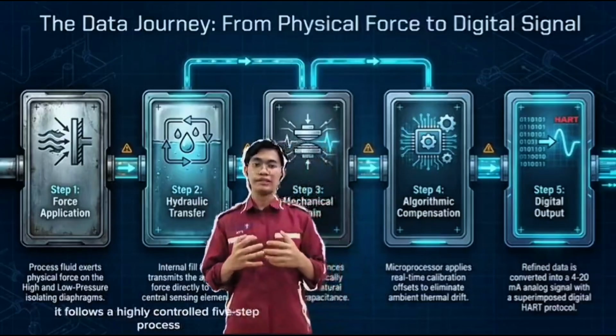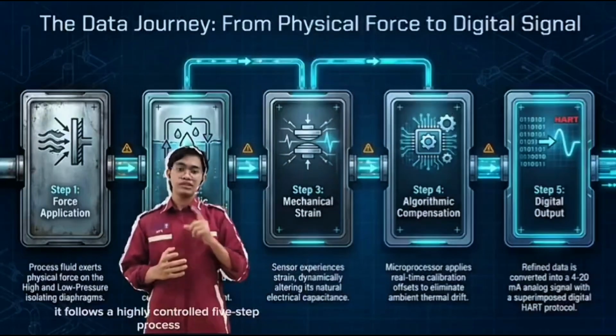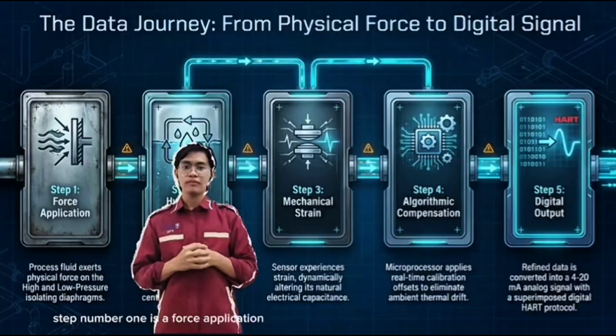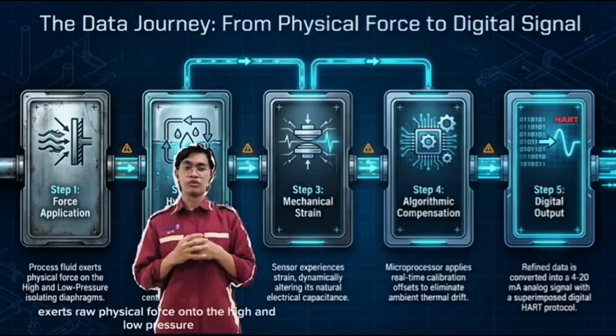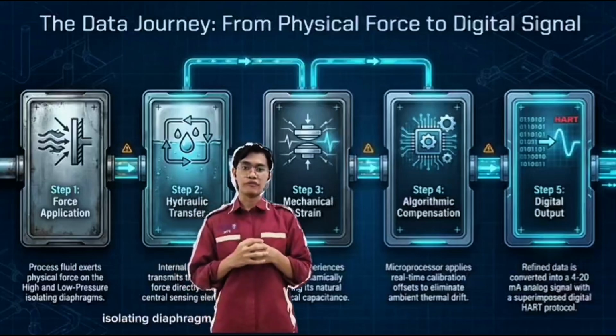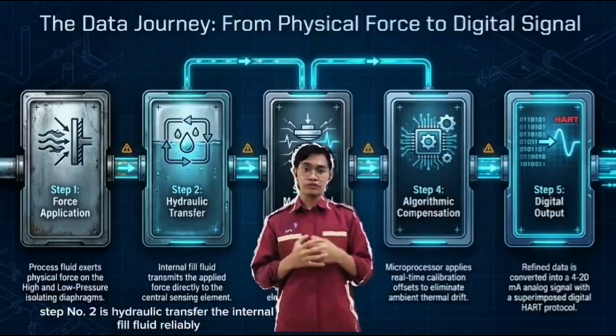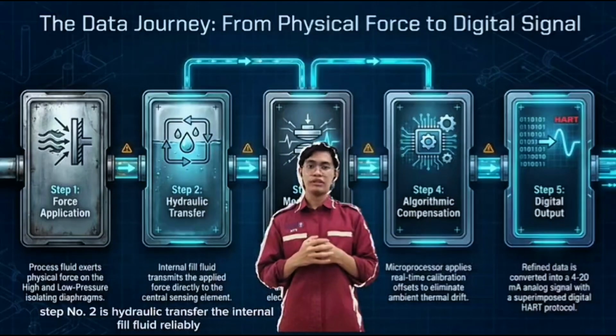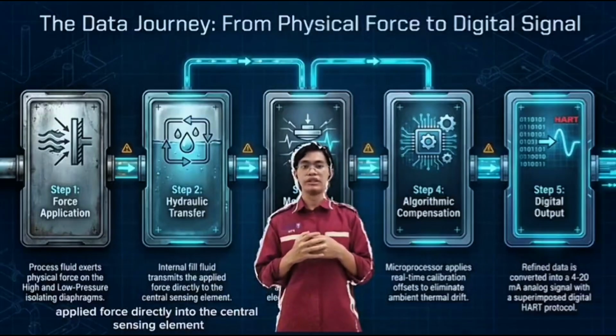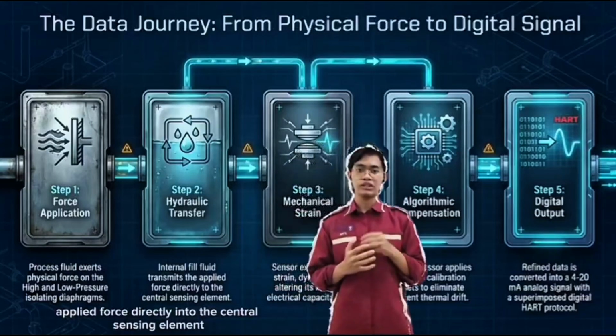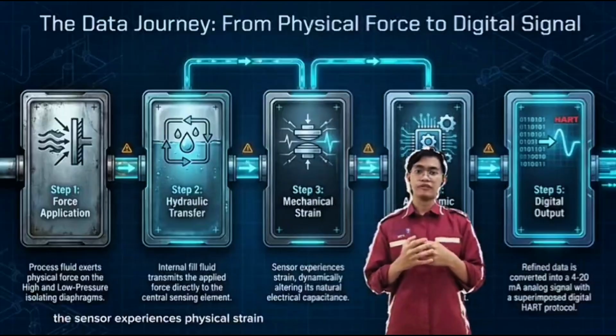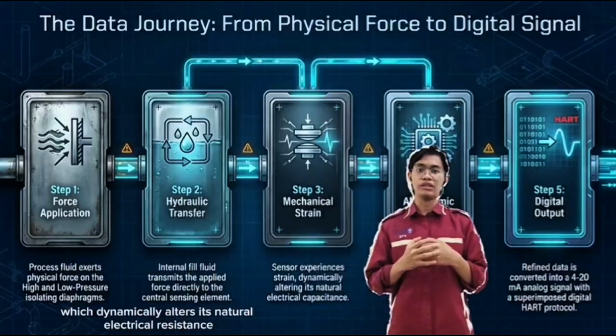It follows a highly controlled 5-step journey. Step number 1 is force application. The process fluid exerts raw physical force onto the high and low pressure isolating diaphragms. Step number 2 is hydraulic transfer. The internal fluid reliably transmits the applied force directly into the central sensing element. Step number 3 is mechanical strain. The sensor experiences physical strain which dynamically alters its natural electrical capacitance.